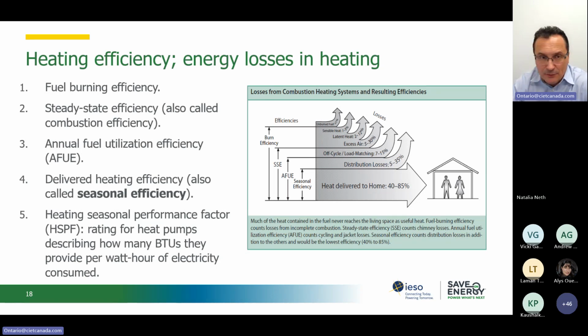And this is a chart I found in one of the literature resources that shows, maybe the numbers are debatable, but it shows a clear progression from the total energy available in the fuel that gets through combustion, converting to heat, and that's the burning efficiency that we see on the chart there, which is as much as we can get out of this chemical energy. The problem is sometimes we have incomplete combustion, and that's a little bit of unburned fuel that's left in the flue gas. Manufacturers tend to design this equipment for zero unburned fuel, but through tuning, through operational conditions, there might be some form of fuel left unburned. Anyway, this is a small component. It should be insignificant, less than 1%.